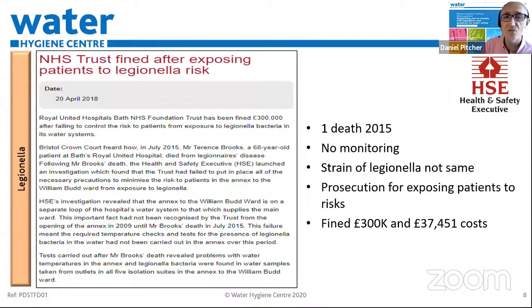Interestingly, the strain of Legionella found within the water system was not the same Legionella that resulted in the patient's death. But the HSE concluded there was significant and sufficient evidence to prosecute the trust for exposing patients to the risk from Legionella bacteria in its water systems.